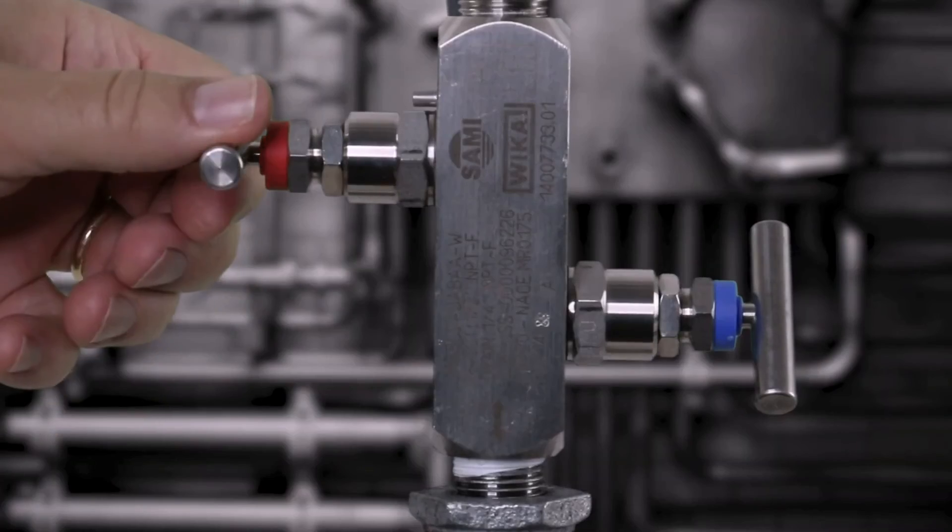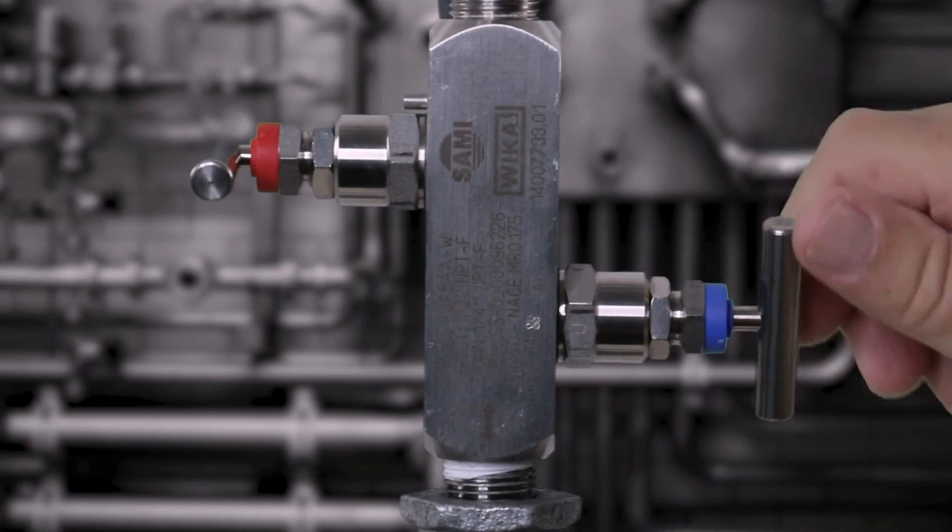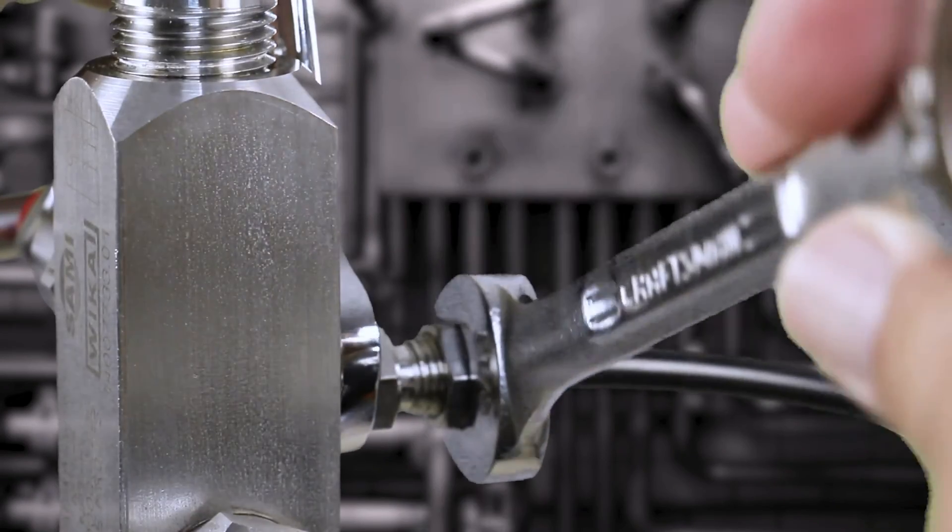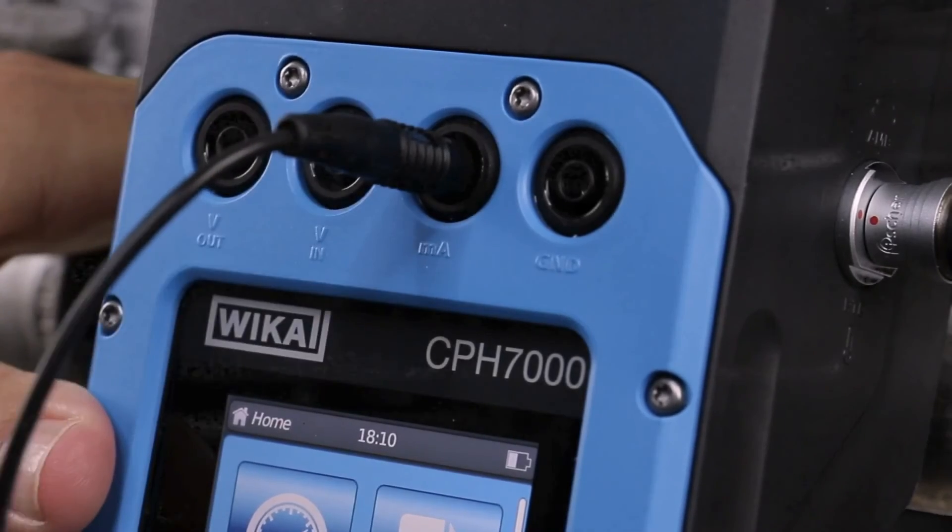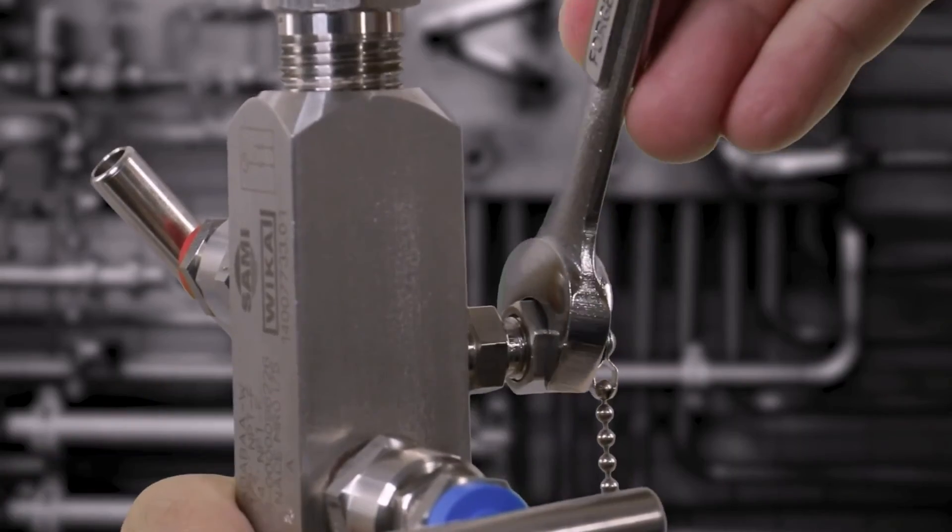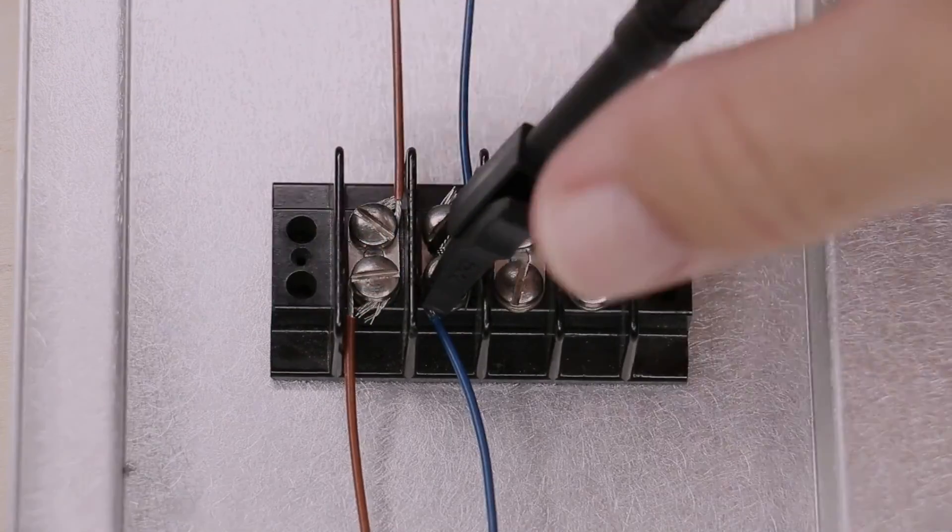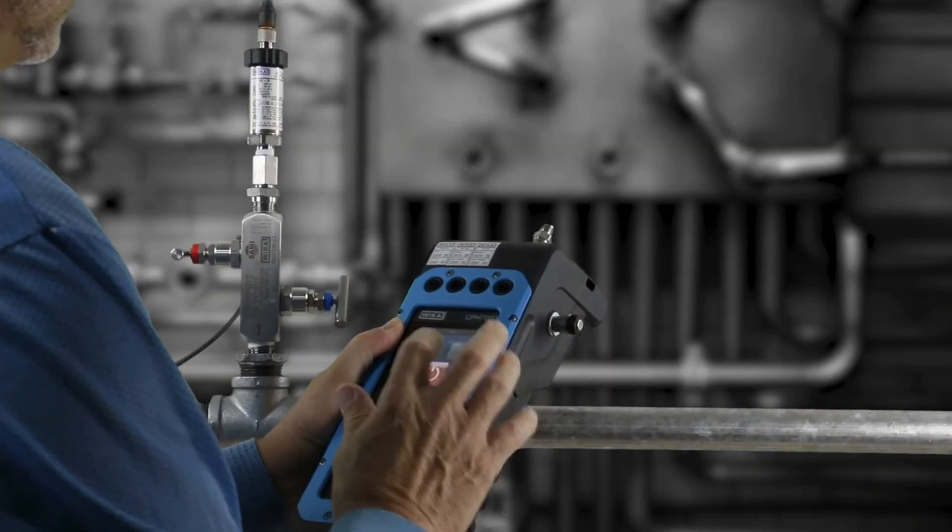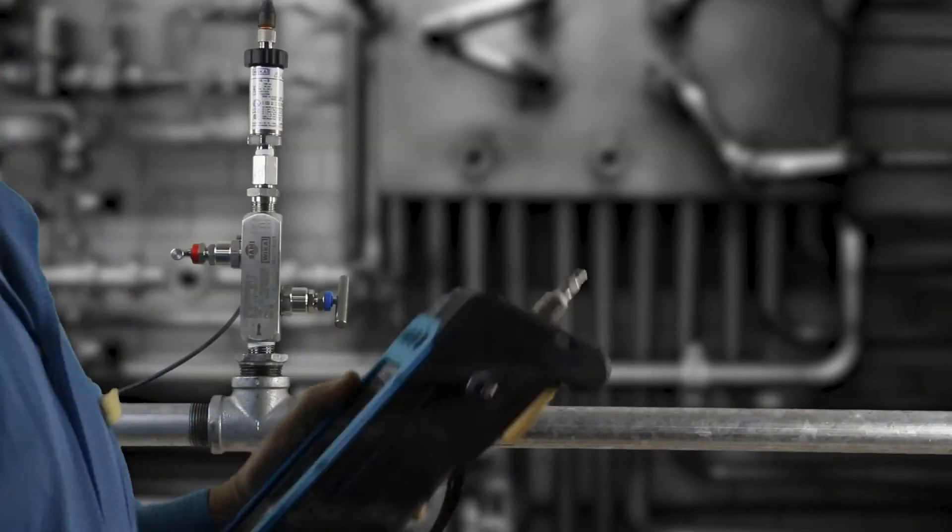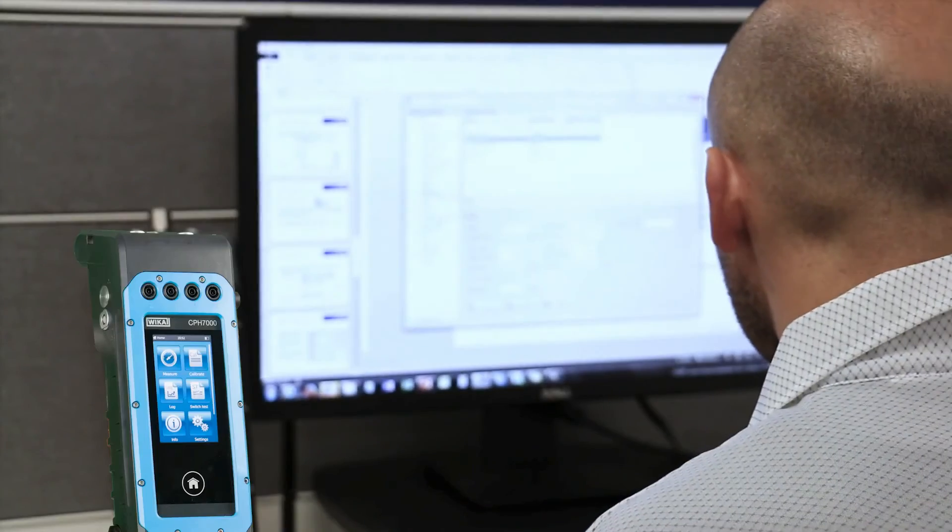When the calibration is complete, close the bleed valve and open the block valve. Disconnect the tubing and the test leads from the transmitter and the process. Replace the cap on the test port. Secure the electrical connections and repower the loop. Collect and record the calibration data using WIKA-CAL software.